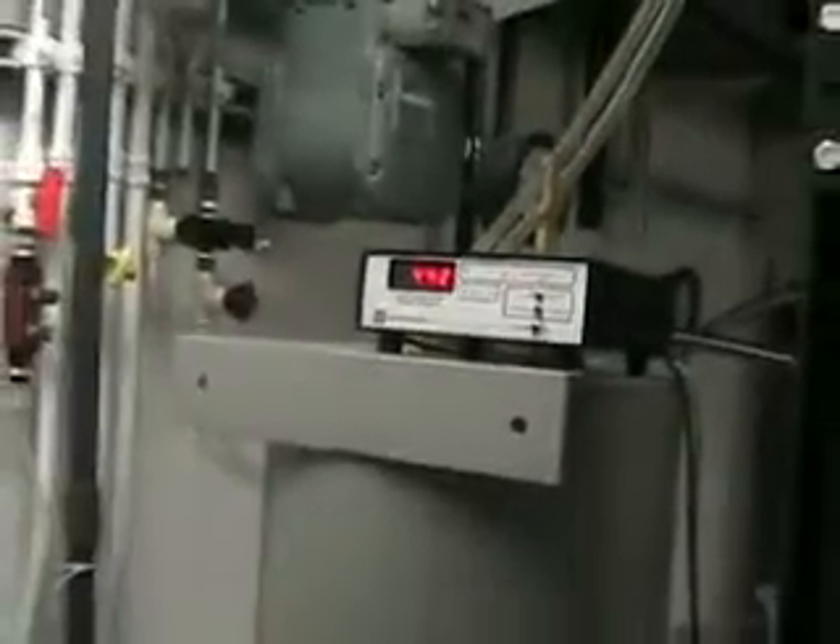Can you give us a brief of what the state is right now? So we finished transferring helium. We stopped about a couple hours into it when the sorb temperature had gotten to 20 Kelvin below, so we put the heater on the sorb to keep it above 20 Kelvin. I waited another half an hour, then pumped out the vacuum can with the diffusion pump for half an hour, stopped transferring during that time. Then I sealed the vacuum pump, started transferring again, and let the sorb cool down to below 8 Kelvin. The sorb is now pumping on the vacuum can and we finished transferring. Our level is at 44.2 centimeters. It should last at least a day — about 36 hours.